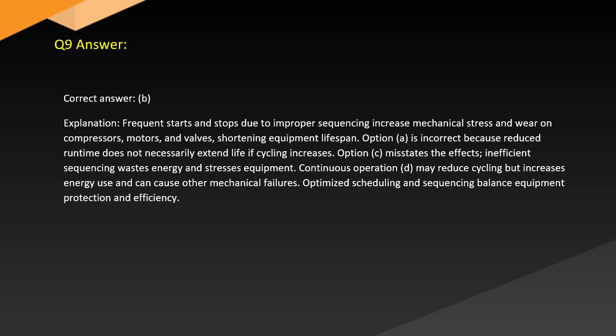Answer. Correct answer: B. Explanation. Frequent starts and stops due to improper sequencing increase mechanical stress and wear on compressors, motors, and valves, shortening equipment lifespan. Option A is incorrect because reduced runtime does not necessarily extend life if cycling increases. Option C misstates the effects. Inefficient sequencing wastes energy and stresses equipment. Continuous operation, D, may reduce cycling but increases energy use and can cause other mechanical failures. Optimized scheduling and sequencing balance equipment protection and efficiency.